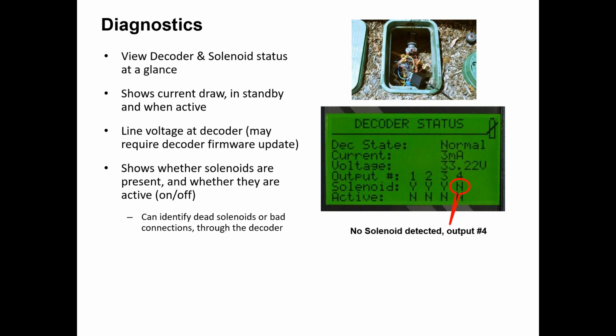As for your one below where it says current, if it's just sitting there dormant, it's typically around 3 milliamps. You can look at your line voltage at the decoder. So on this one where it says 33.22 volts, that's right where it should be. It's right in the sweet spot. Typically, I tell people that it should be between 30 and 35 volts. And you can show this one right here is actually a 4-station decoder that it's hooked onto. You can see if it's got a solenoid attached, and you can see if it's turned on or not. And see the yes, yes, and no on number 4. Number 4 port is not being used. It's only 3 out of the 4, and none of them are turned on.